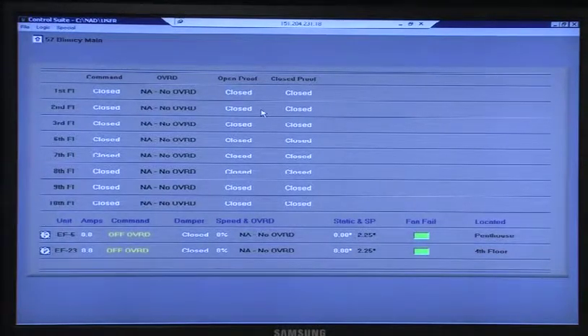Well, let me ask you this. If I went to here and I hit override and I overrode that damper on, I'm gonna see that command go to open. Is that for construction exhaust? Yes, open. Maybe you should make that command on-off instead. Right now it's closed. Why is it closed? What is my command? What am I commanding? Well, you'd be commanding it to open on that floor. So if you have construction on that floor, you want to open the construction exhaust.